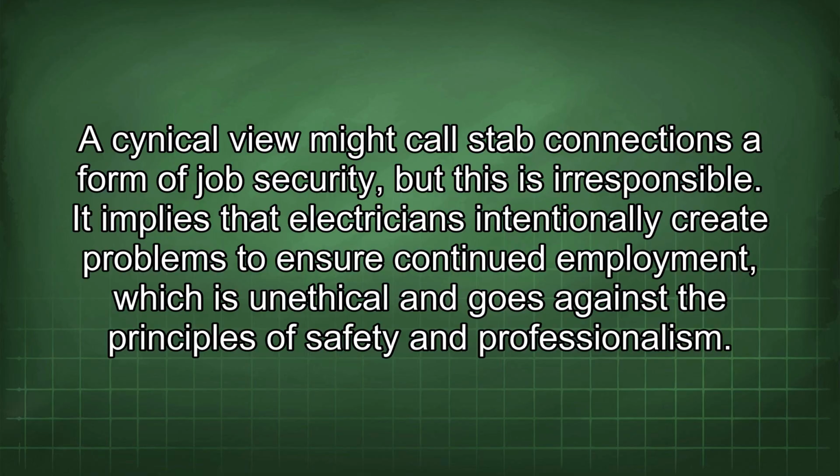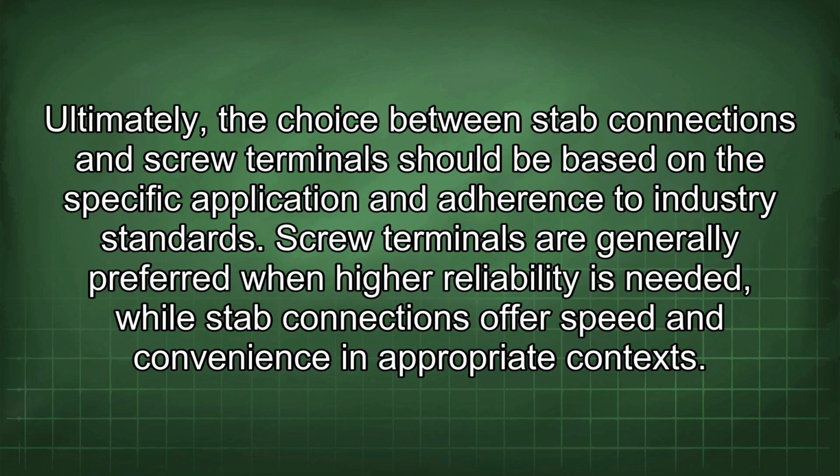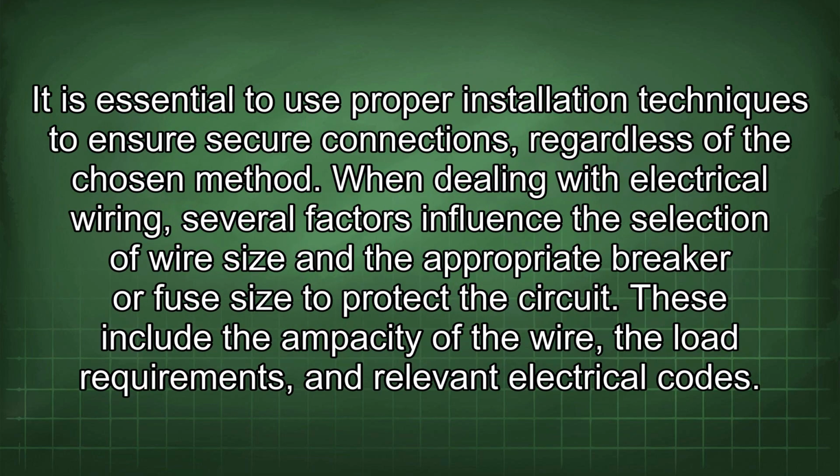safety and professionalism. Ultimately, the choice between stab connections and screw terminals should be based on the specific application and adherence to industry standards. Screw terminals are generally preferred when higher reliability is needed, while stab connections offer speed and convenience in appropriate contexts.